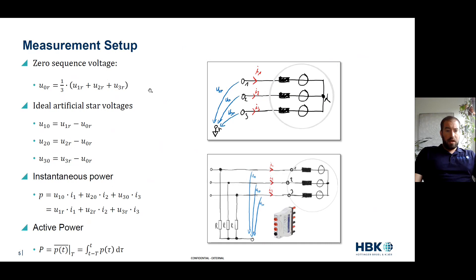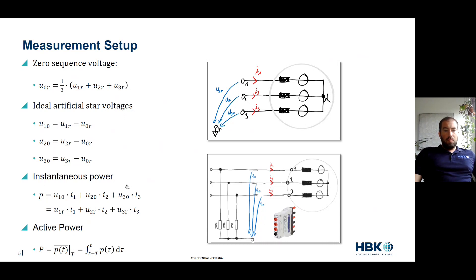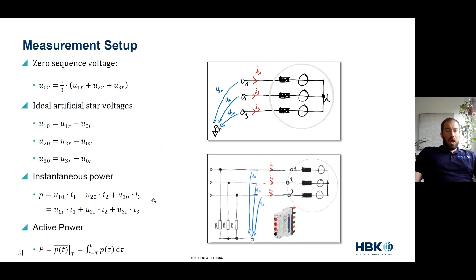The measurement setup: we're measuring the three phases of current and three phases of voltage. We're using an artificial star — faking out the neutral — which is a perfectly accepted way of doing it. We're looking at the instantaneous power: U1 times I1, U2 times I2, U3 times I3, and so on. Our active power is the average over a time period on a cycle basis. These are just the definitions for active power to set the scene.